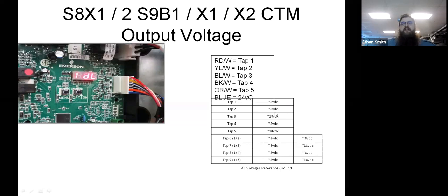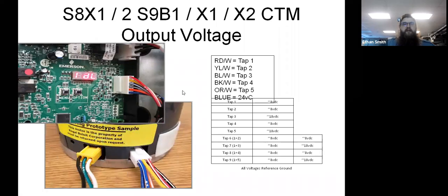Now this is a DC voltage chart out of a Trane American Standard unit. We've got the 5 wires for low voltage that go out to the motor off of that control board. So that's just an example. There are other manufacturers doing this the same way. Okay, so this is just a picture. They may not always have those giant white plugs.